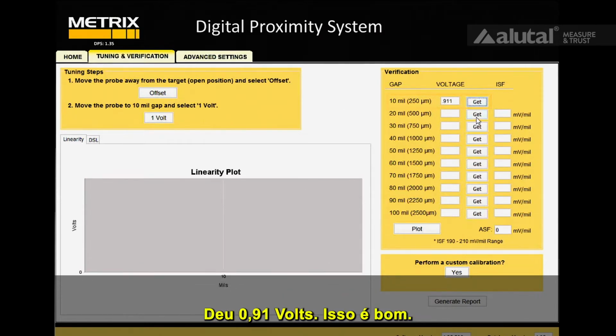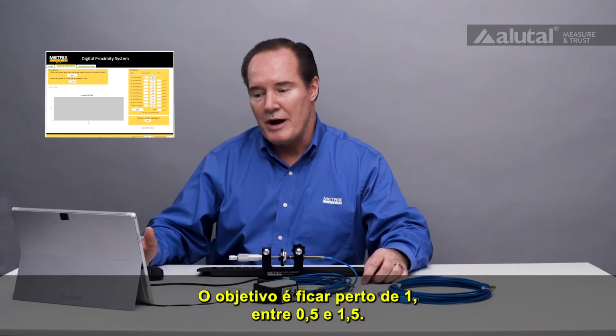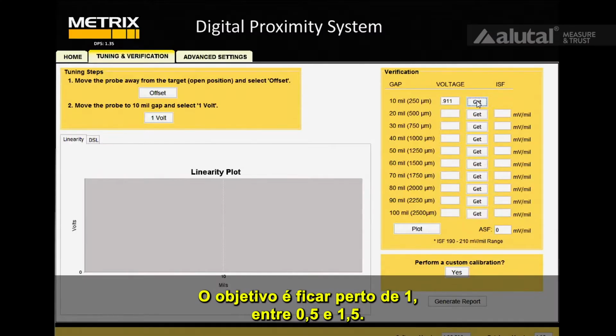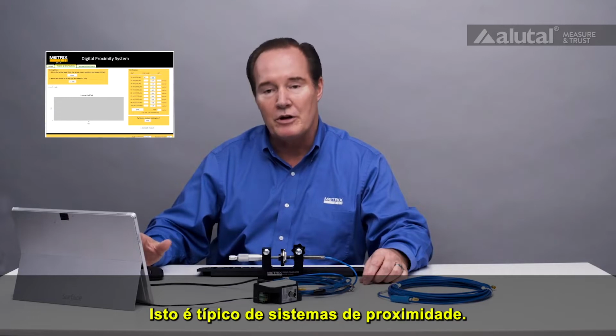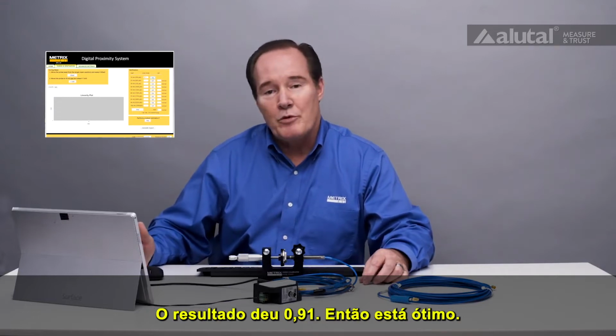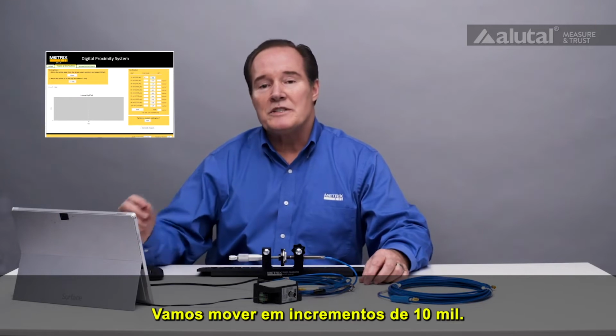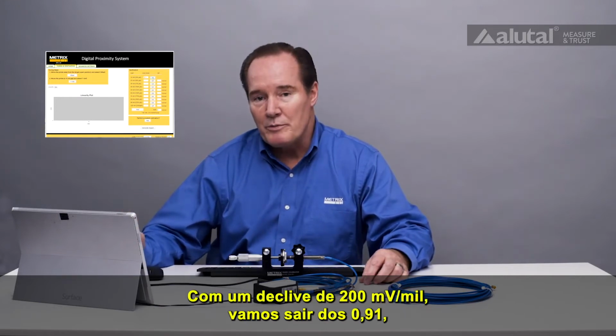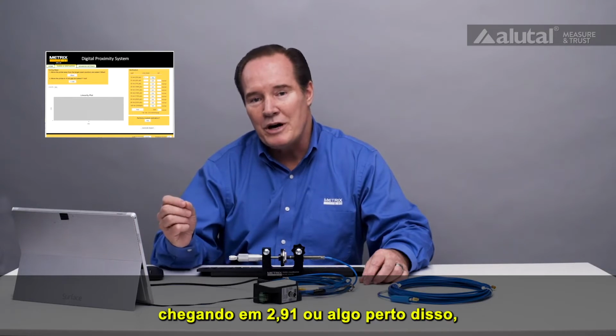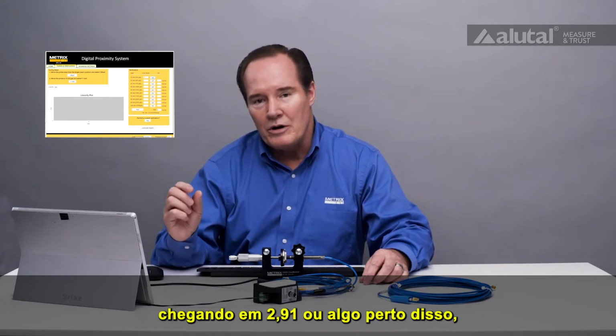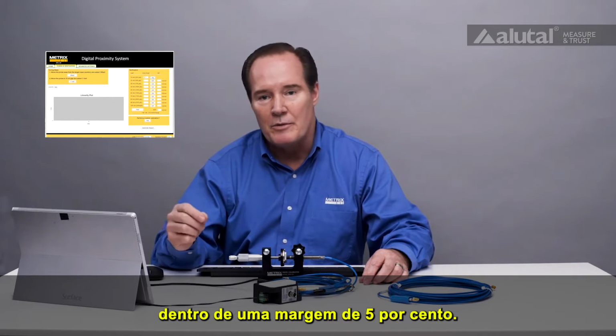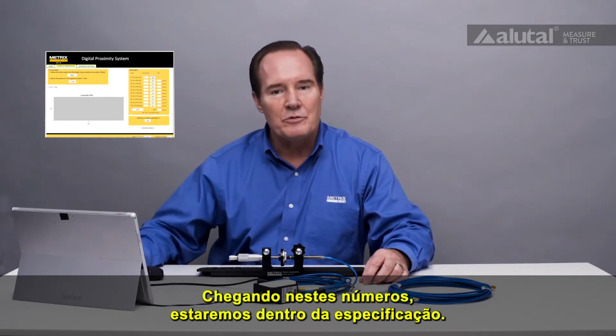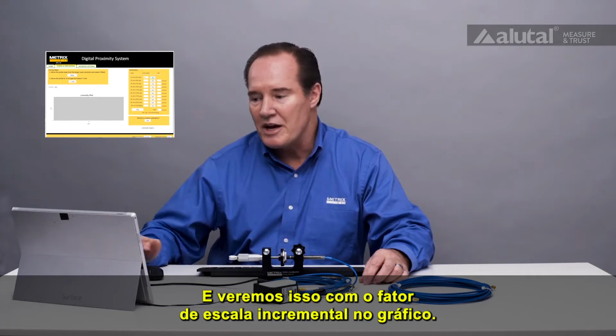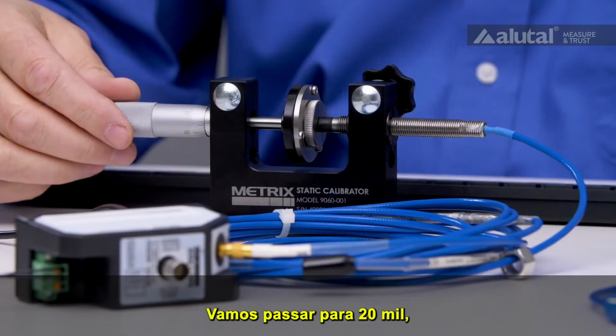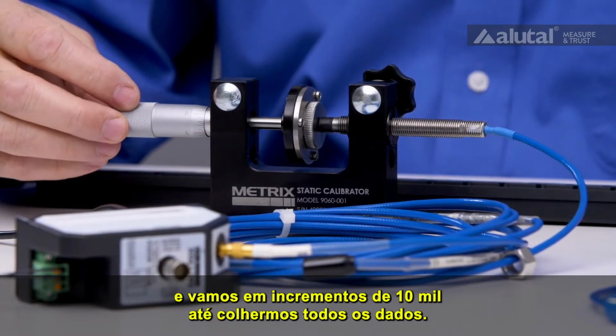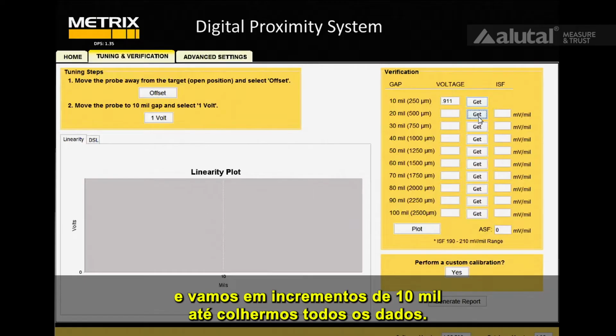And at 0.91 volts, that's good. We'd like it to be right at near close to 1, between 0.5 and 1.5. That's typical of proximity systems. And we have 0.91, so that's good. So we're going to move in 10 mil increments. With a slope of 200 millivolts per mil, we're going to go from 0.91, we should go to 2.91, or close to that, within 5% of that number. So as long as I'm doing that, that will be in specification. And we'll see that with the incremental scale factor here on the plot. So let's go ahead and go to 20, and then we'll just do this in 10 mil increments until we get all the data.